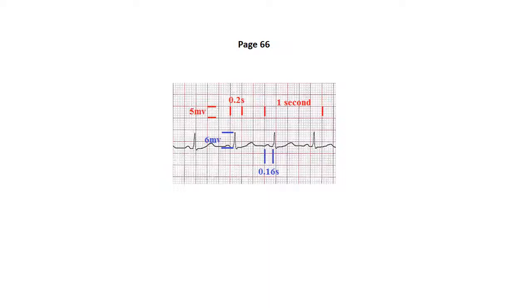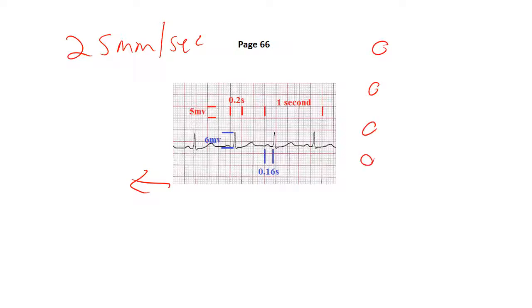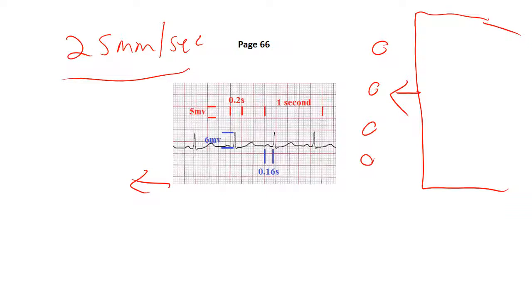What you have to understand is that an EKG machine has a standard sweep speed of 25 millimeters per second — that is how fast the paper is moving under the pins. On most EKG machines, you have four pins in a perfectly straight line, and the actual EKG paper simply slides to the left at 25 millimeters per second. Each of these four pins graphs electricity, moving either up or down the page, while the left-to-right motion is controlled by how fast the paper moves.